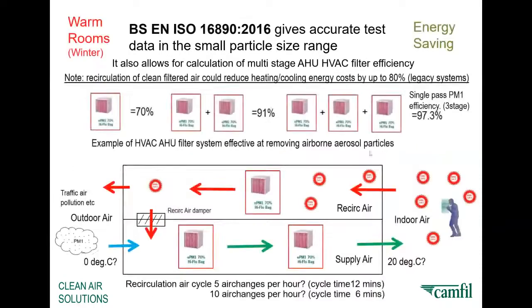So if you look at this, you can see here a multi-stage filter system. There are, as I say, hundreds of thousands of these legacy systems that might have air boxes for mixing air, recirculation air. They may not have heat recovery systems built in. They may not have heat wheels. They may not have run-around coils, but they do have a damper system where they could recirculate the air. And if they do have that, rather than having the knee-jerk reaction of turning off recirculation, if you filter the air coming back through with a 70% ePM1 rated filter and have it introduced upstream of the supply air side filters coming back into the building, that would be 3 stages of air filtration, as you can see here, before the air makes the circle through those and comes back into the indoor space.